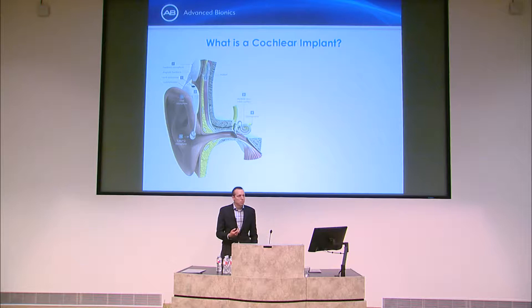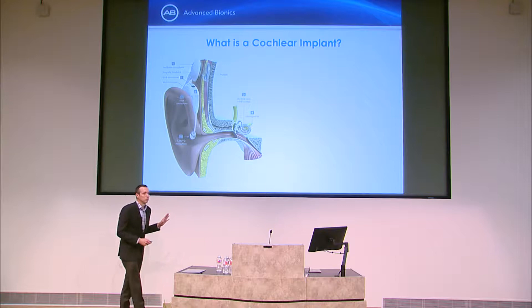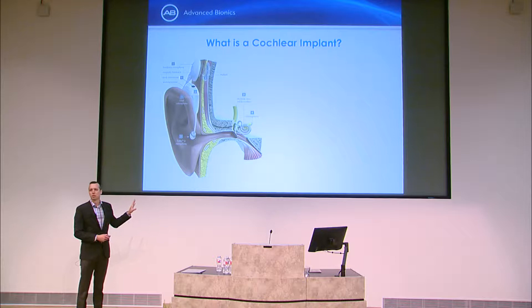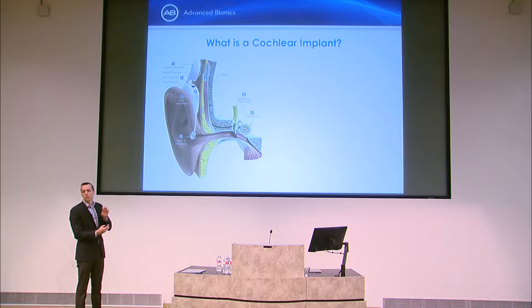I set up this talk to share some of the things we've learned over the past 25 to 30 years in this space. A cochlear implant is for people that are profoundly hard of hearing or deaf, experiencing sensorineural hearing loss. The device starts with an external microphone on a body-worn component that goes to a sound processor powered by a battery behind the ear.